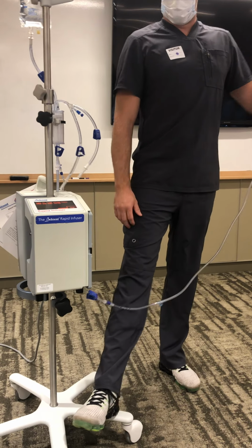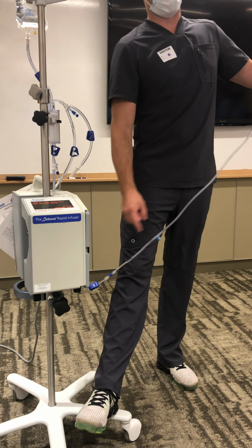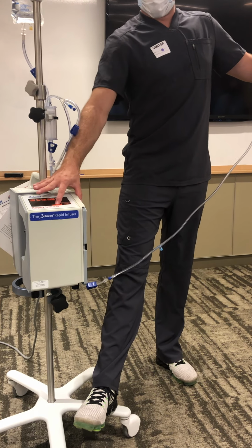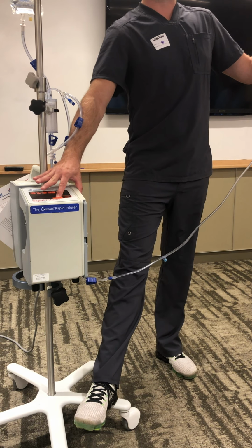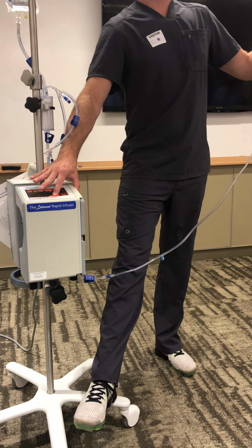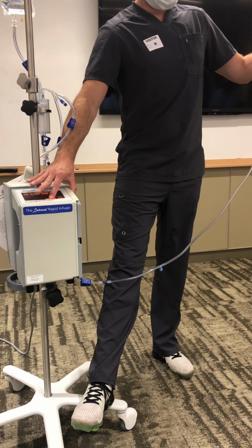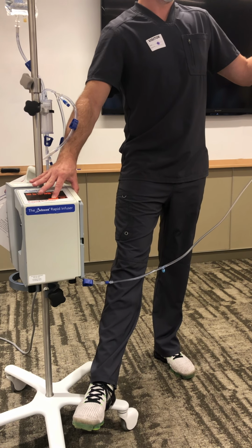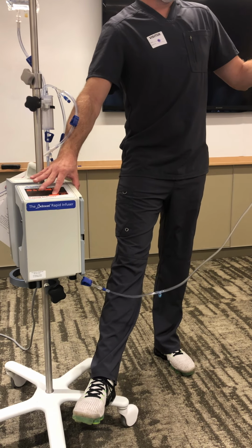If I press the patient line prime, you'll see fluid start to come through at 50 mLs a minute. However, if you press and hold, it'll go 4 times faster at 200 mLs a minute. Chances are when a rapid infuser comes out, this is what you're going to want to do because you need it in a hurry. However, you do have both options.